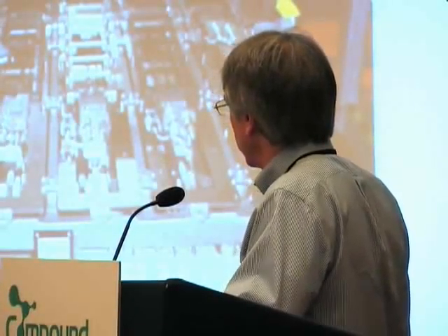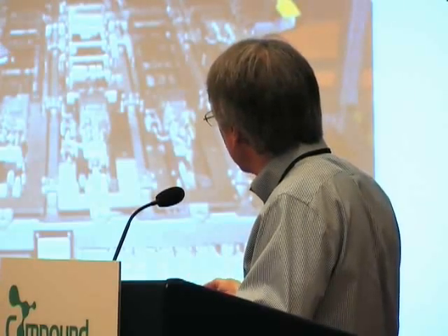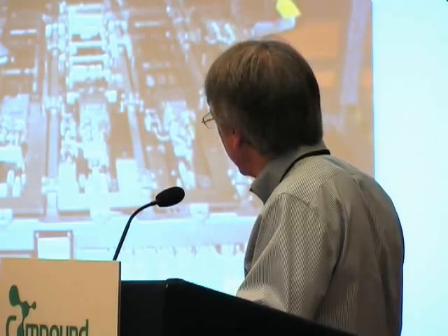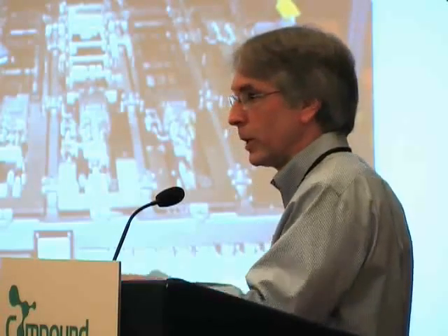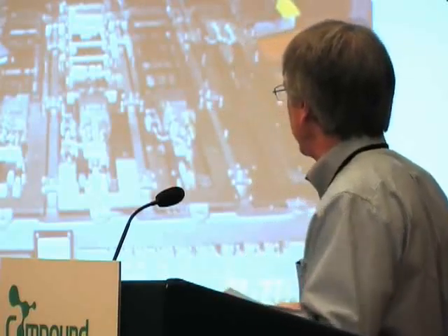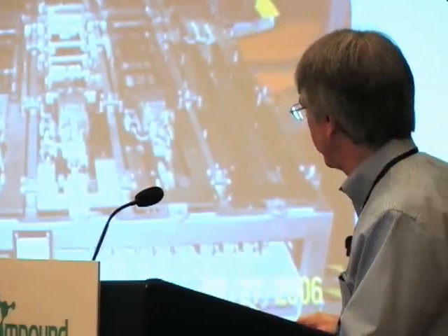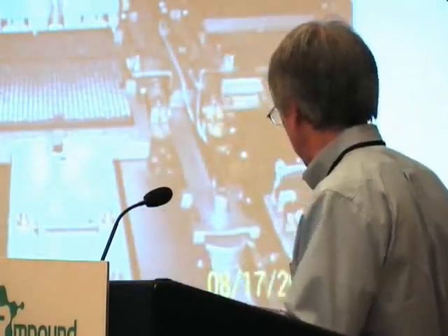There's a cytomat carousel system and a diving board, and this device here comes over, kind of a fork-shaped device. It's holding a rack right now. It pivots on this point, so it'll come around here, pick up a plate, bring it all the way back here, and then there's grippers on that head that will pick it up and move it onto one of these trays. If we were bringing in the 96 well plates, it would be held here by these forks, but right over this plate reader, so we could read all the barcodes and verify those barcodes before we moved any of the tubes.